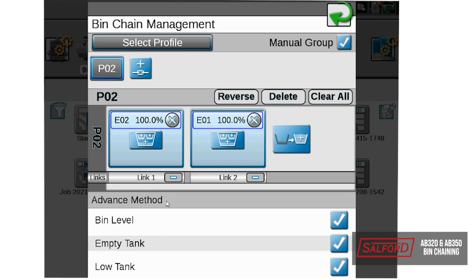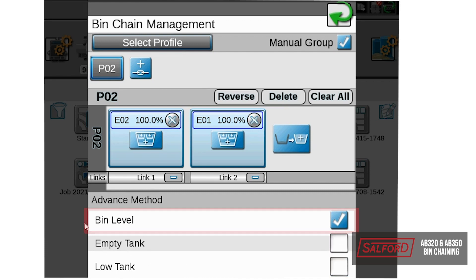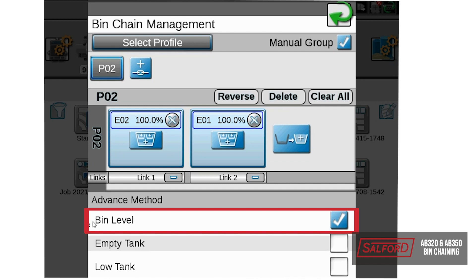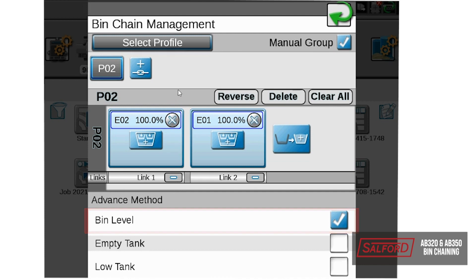For our advanced method, we will uncheck our low level tank and empty tank. We will want the machine to advance based on the bin level signal, so once the bin level signal goes off, it will then switch to the next link.